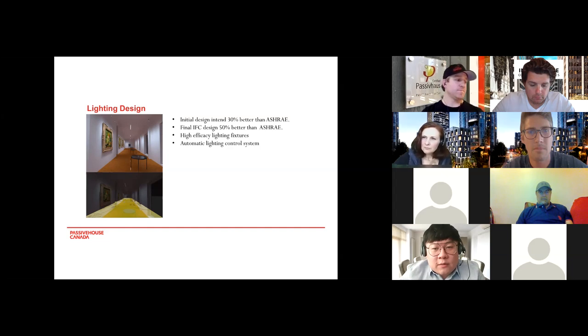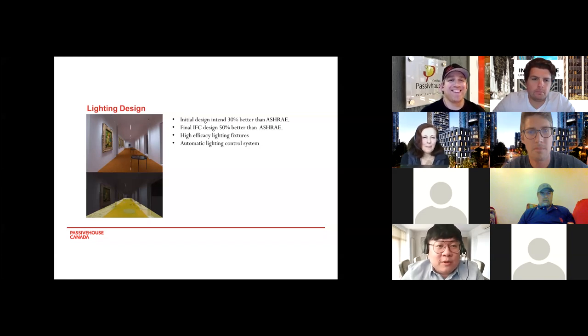As usual, we started this project by targeting the LPD as 30% better than ASHRAE. And the design was achieved by using high efficacy LED lighting fixtures and automatic lighting control system. Later in the design stage, we were requested by the Passive House Institute to reduce the LPD from 0.9 watts per square foot to 0.25 watts per square foot, which gave us a lot of headache, between me and Prudence. And we finally pushed that down to, I think, 0.27. And we realized that was the bare minimal life safety requirements for the Canadian Electrical Code.